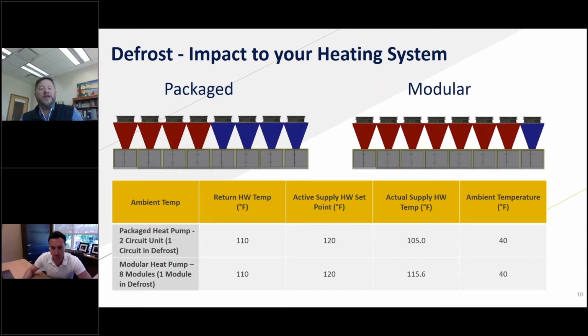When we compare that against the setup that has more smaller units, and if we only allow 1 unit to go into defrost at a time, we have a far different impact. So worst case in that scenario, with the smaller units, whether it's us or another manufacturer, you'd be looking at upwards of 115 and more likely getting closer to that 120. So even while you're defrosting, you're still providing usable hot water that is approaching what your actual set point is. As you can see, I'm doing that at a 40-degree ambient.